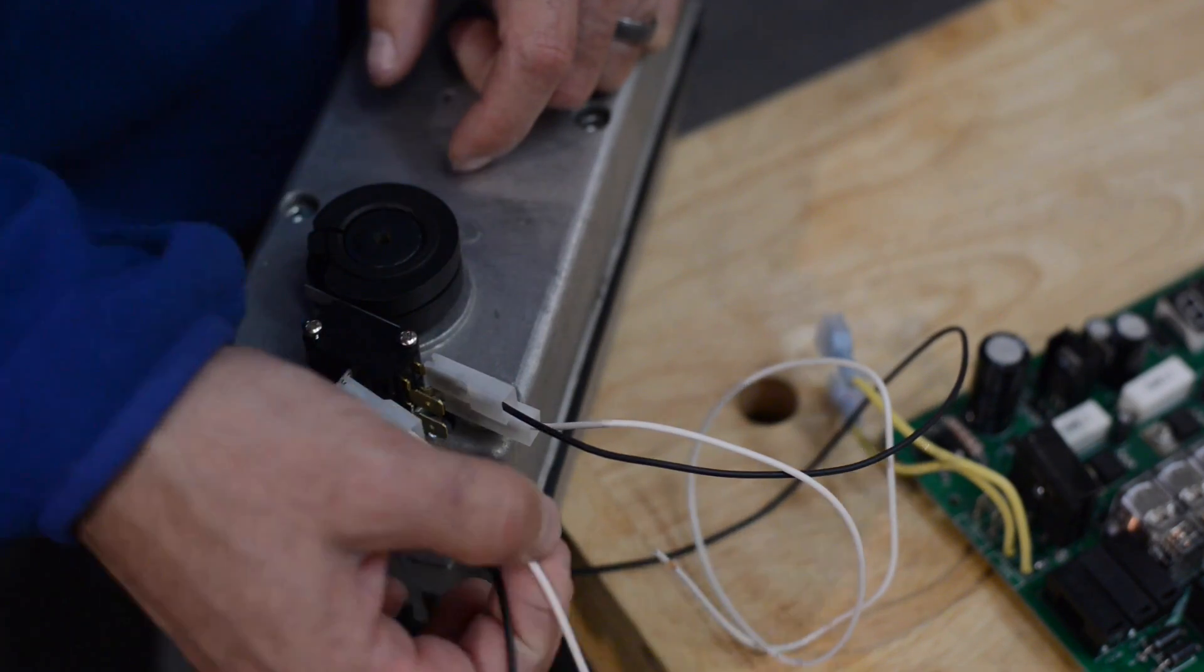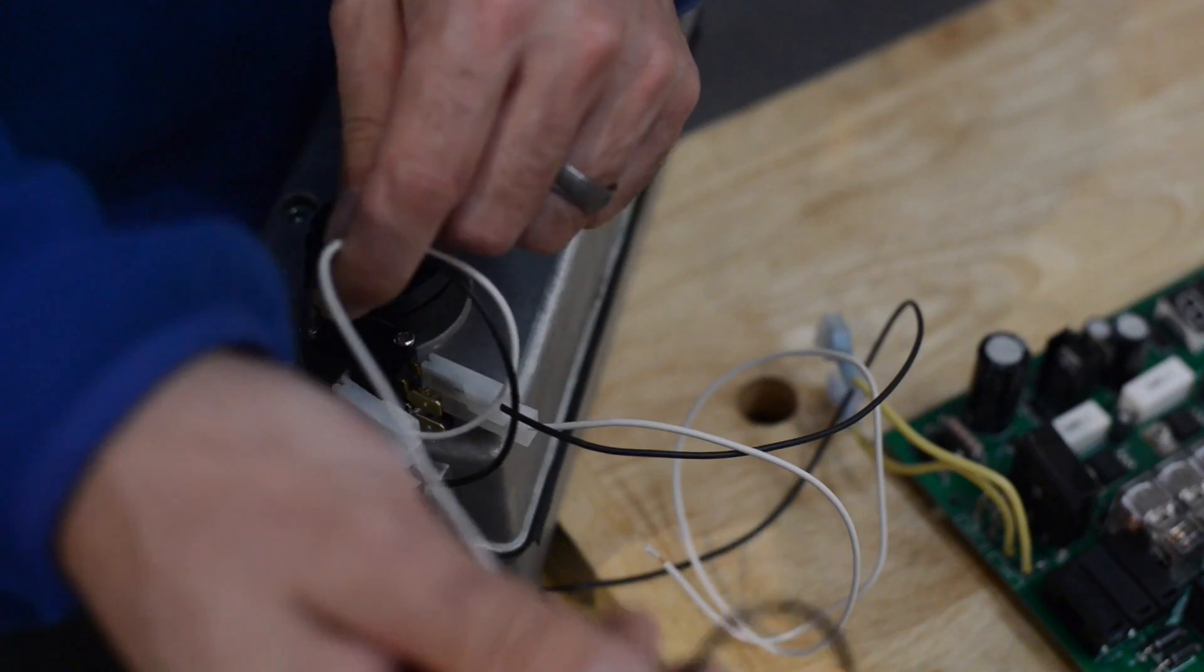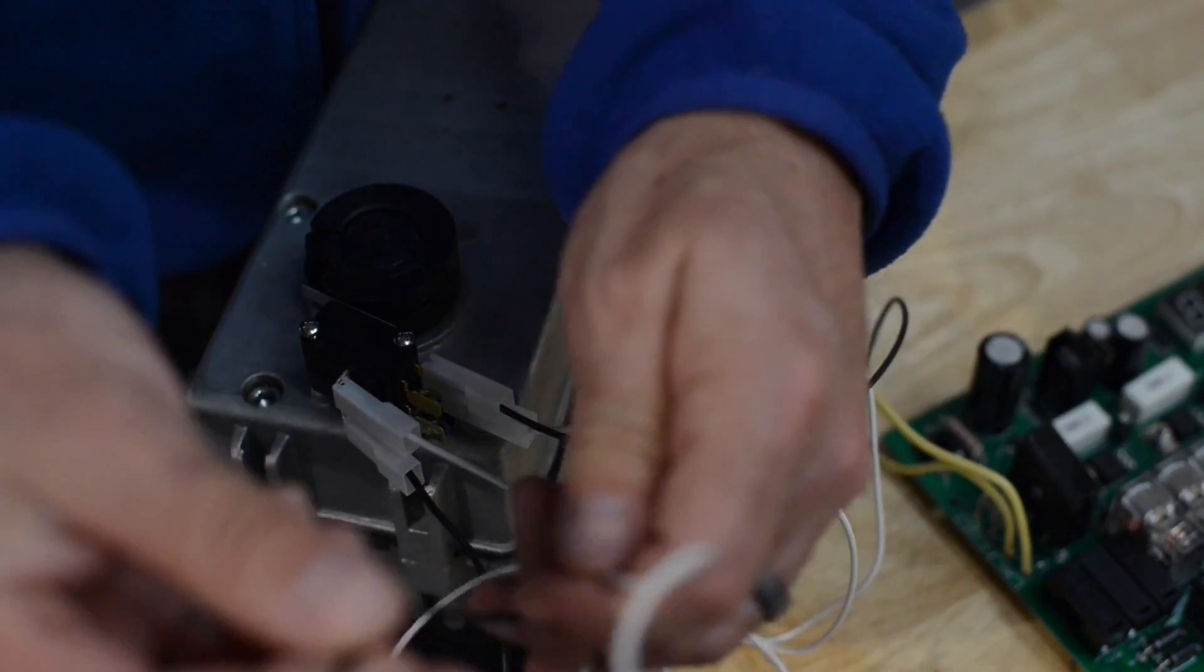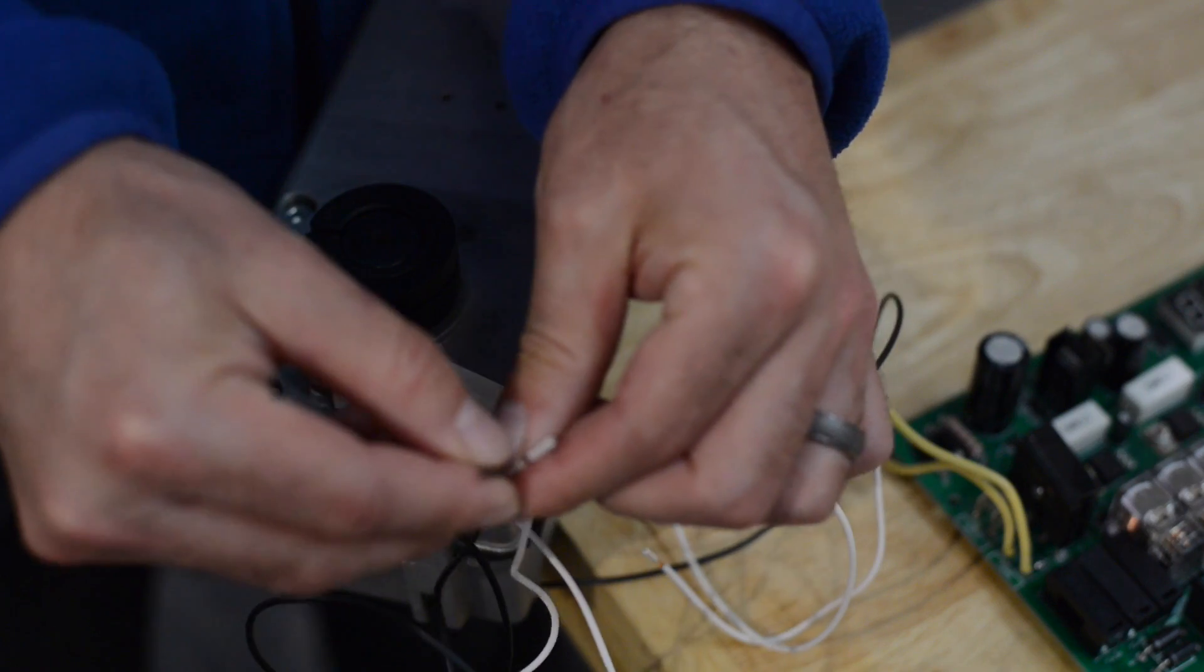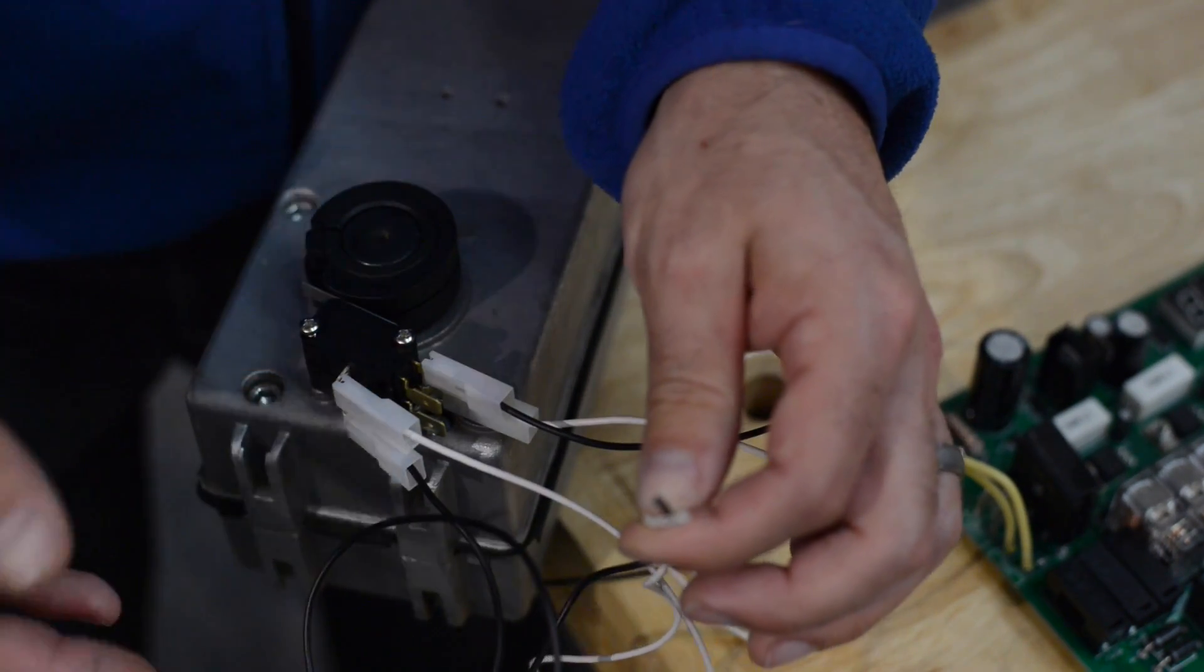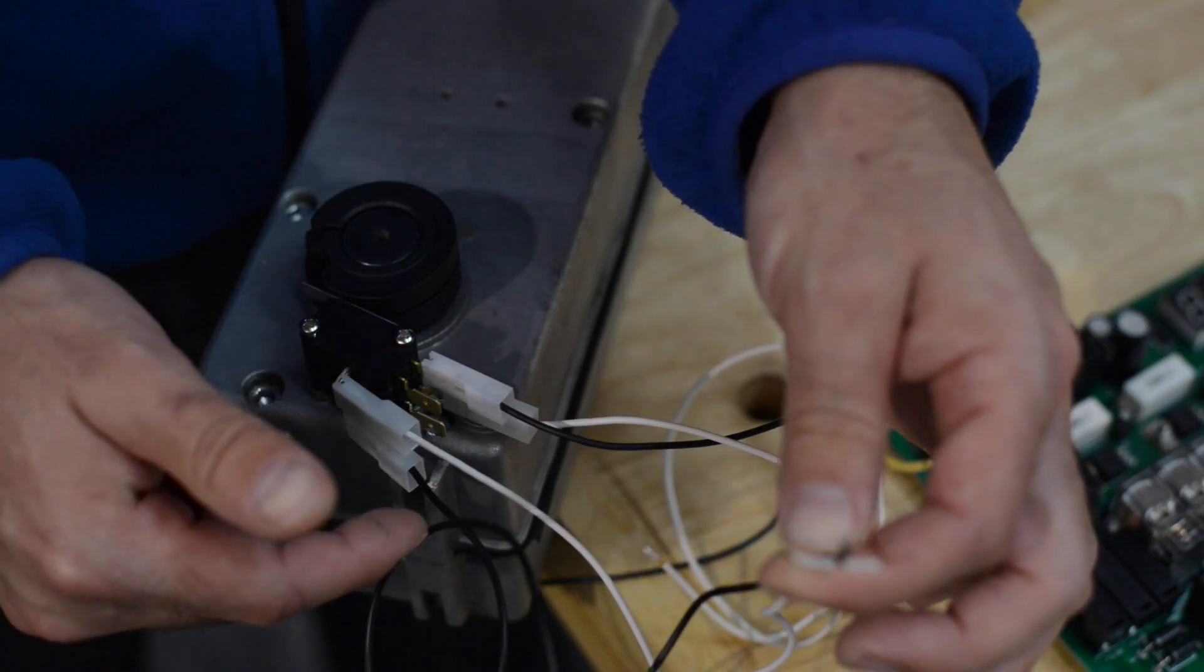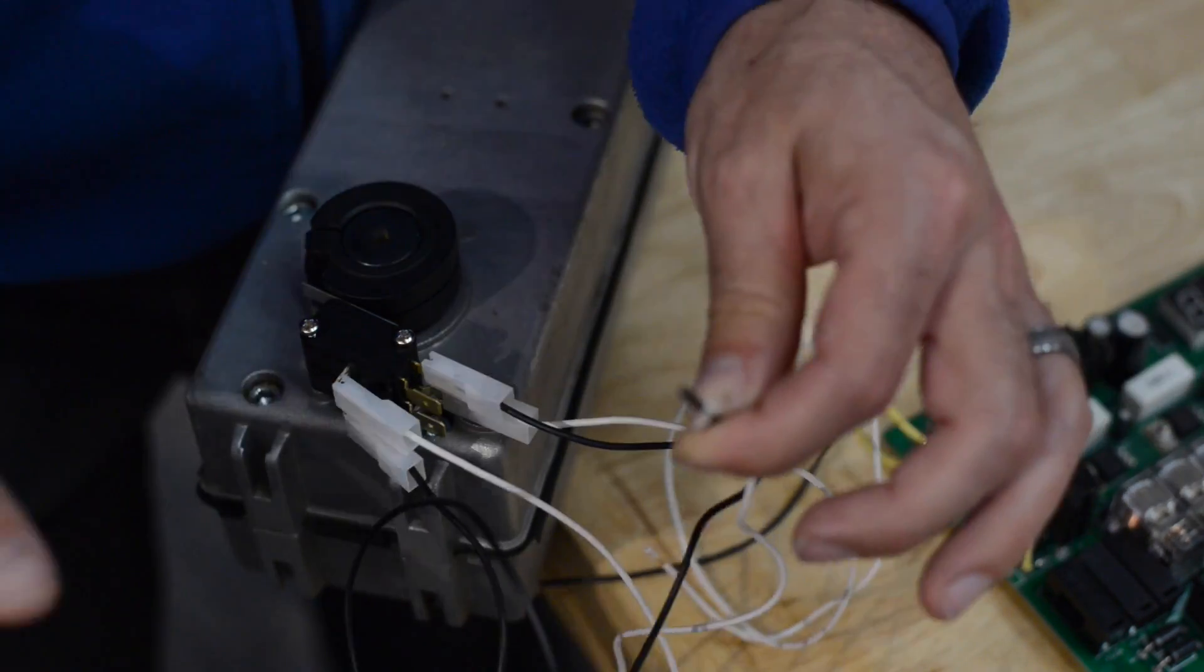Now you want to see what wires these are paired to, because most of the time the wires that come with this go to longer wires that go back to the control board. What you are usually going to find is the two wires from the common are typically joined together to one wire. Because on both the old board and on the new board they went to the same terminal. So on this scenario I purposely mixed up the wire colors because again wire colors do not matter. Ignore wire colors.